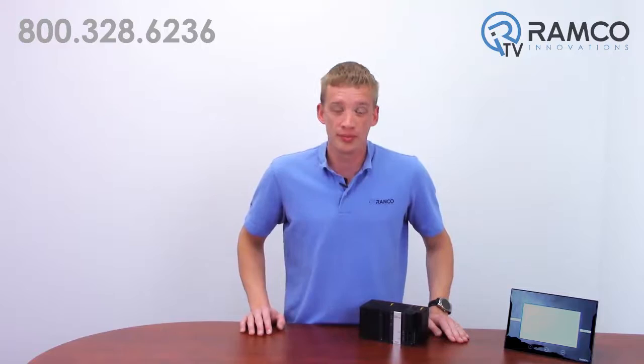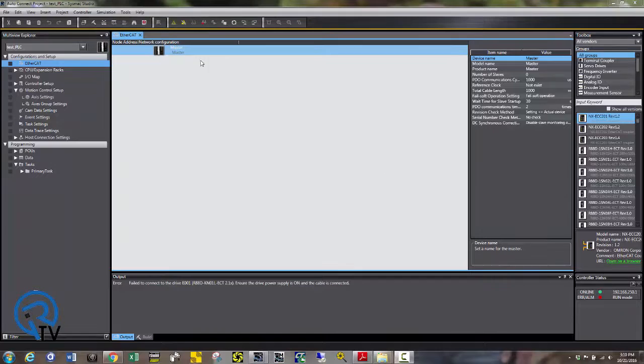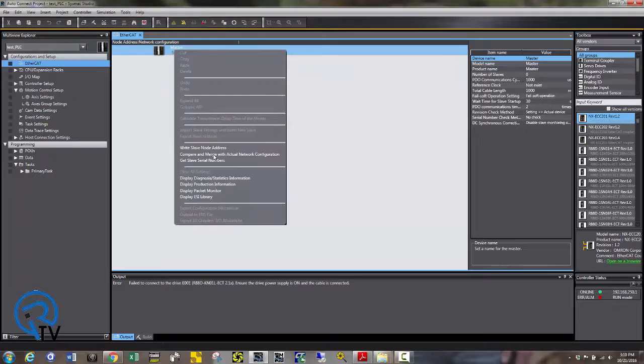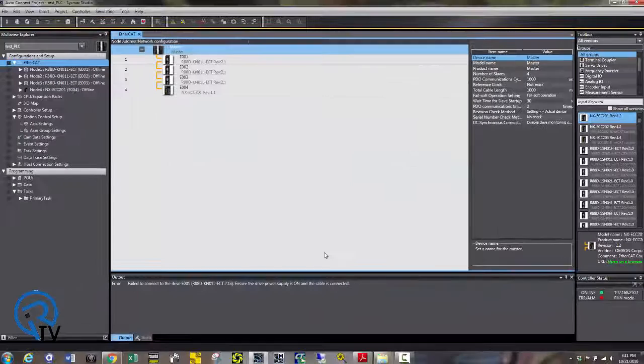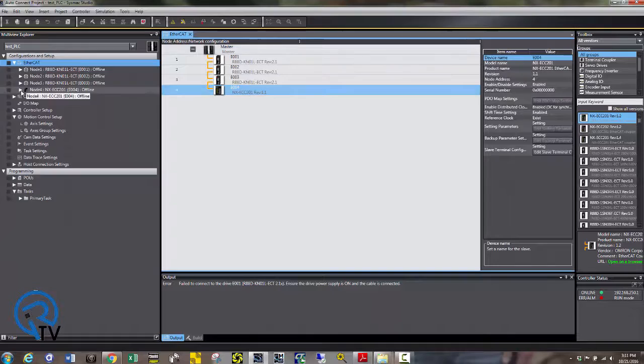I'm going to show you how easy it is to set up the initial setup of a three axis servo system. Once online, we're going to right click on the master and say compare and merge. This is going to go find any axes that is connected to my EtherCAT system. Apply this configuration. And now we can look at each axes and identify their catalog numbers. We can even look at the inputs and outputs that are connected to the EtherCAT coupler.